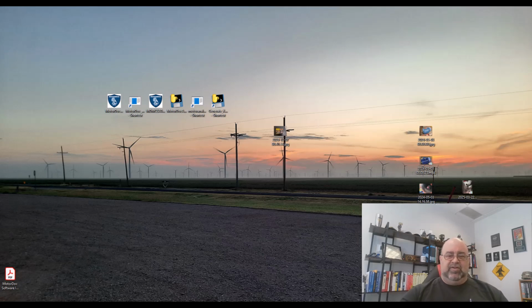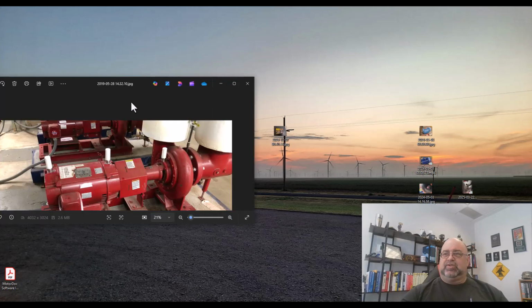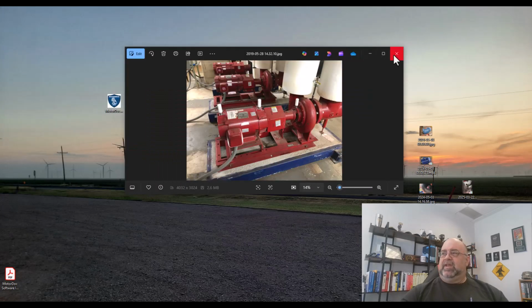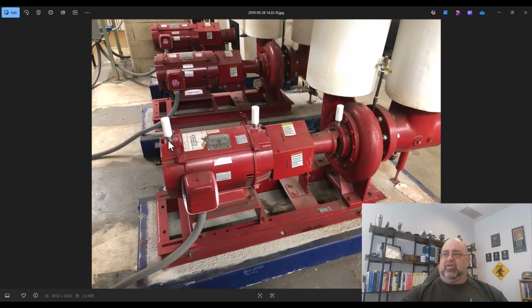Let's see what something - this isn't the best, but this is what I would hope to see, other than the fact that really I'd rather have these horizontal. But I'm relatively over the bearing. I'm not super impressed by this, but still, because of the end shield, personally I would have them right here, right above the bearing, towards the side. You're still going to get a bell effect, you're going to have some losses in your transmission, but even vertical this is not horrible. I'm still going to detect things from the bearings because I'm right over the bearings.